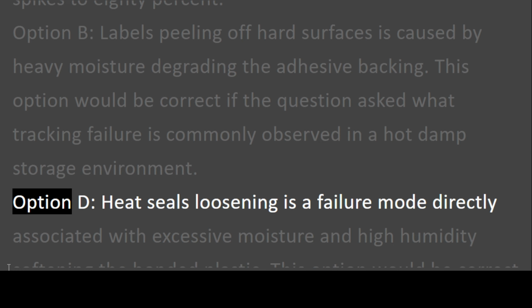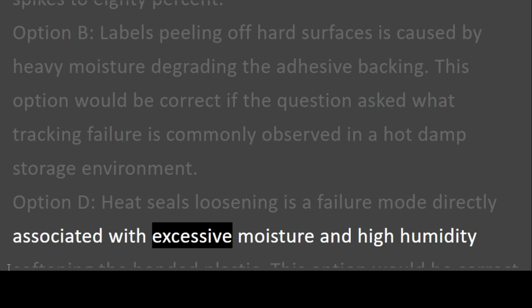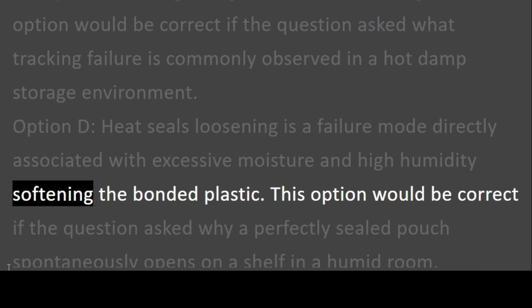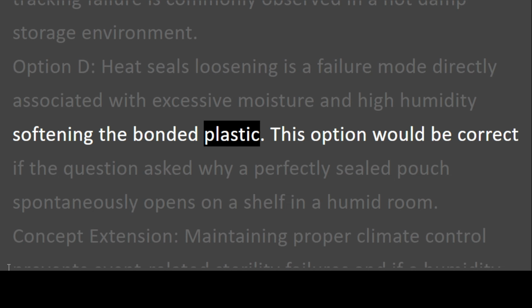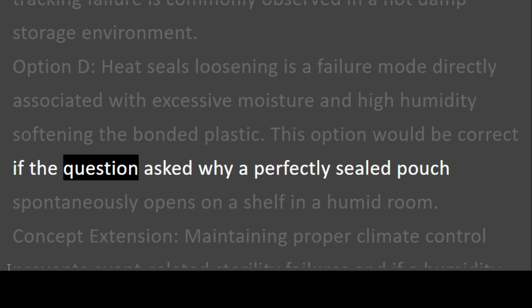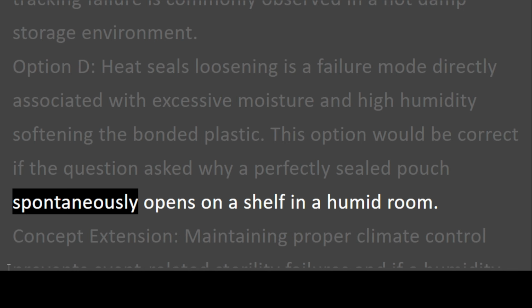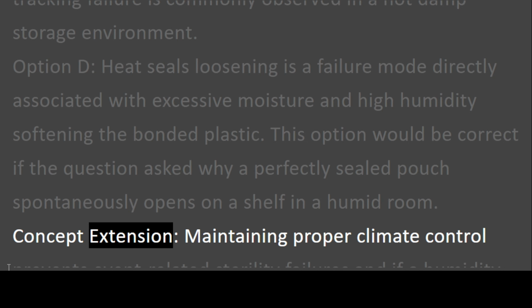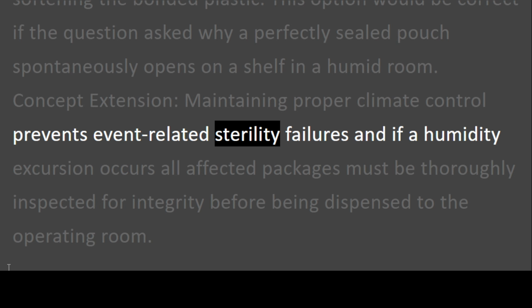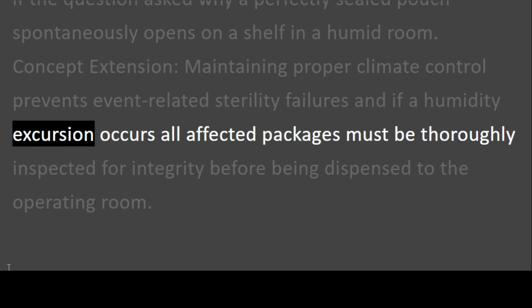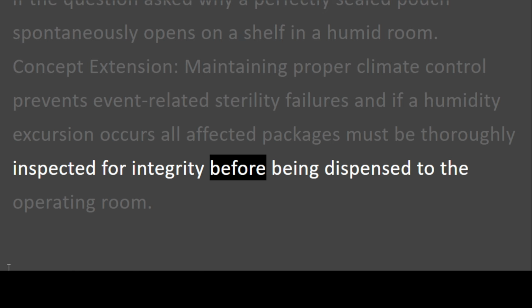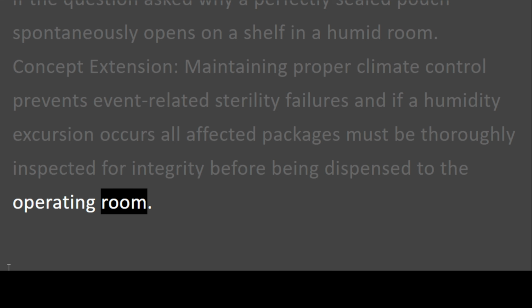Option D. Heat seals loosening is a failure mode directly associated with excessive moisture and high humidity softening the bonded plastic. This option would be correct if the question asked why a perfectly sealed pouch spontaneously opens on a shelf in a humid room. Concept extension. Maintaining proper climate control prevents event-related sterility failures, and if a humidity excursion occurs, all affected packages must be thoroughly inspected for integrity before being dispensed to the operating room.